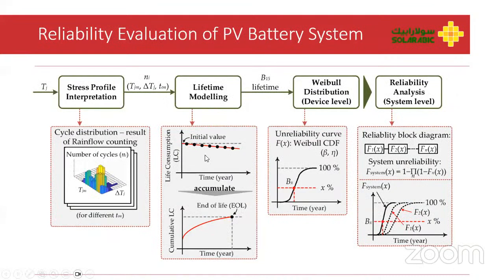So this here is the reliability evaluation model in order to judge the reliability of a photovoltaic battery system. What we do is the stress profile interpretation of all the electrical components within the converters under accelerated aging. And then we try to find out the uncertainties. Based on those uncertainties, we develop a lifetime model. And from that lifetime model, we use different research methodologies, like Weibull distribution, in order to judge and evaluate the overall reliability of the PV battery system.